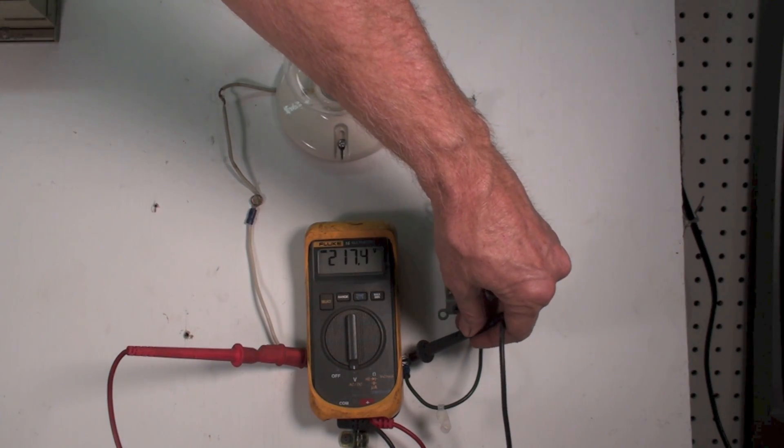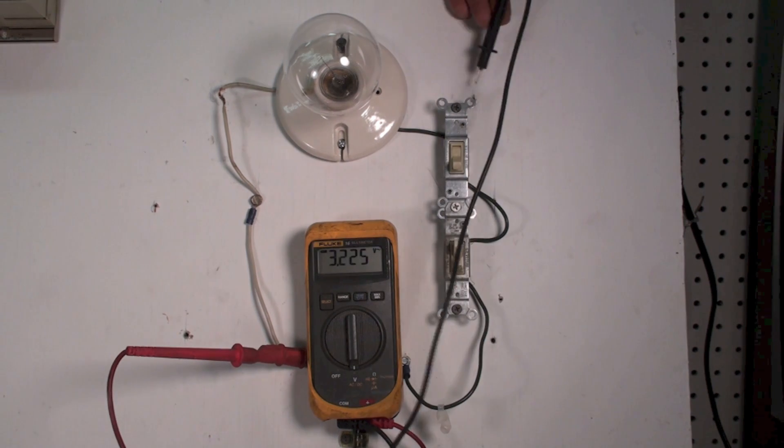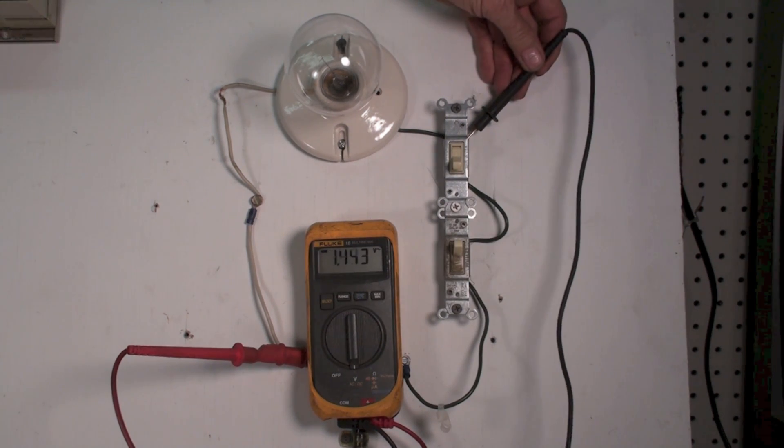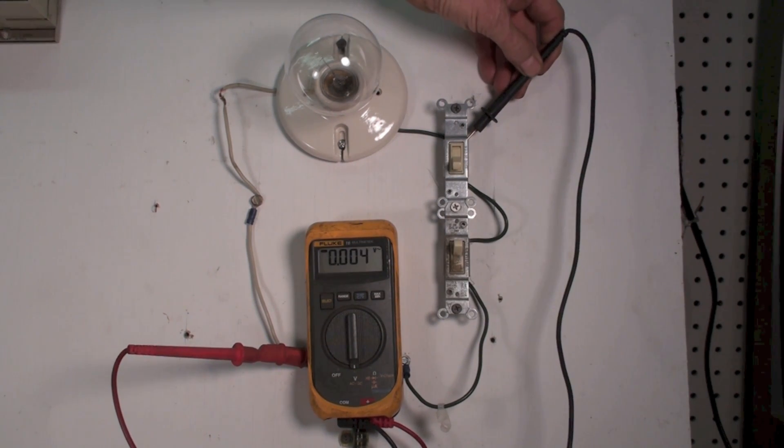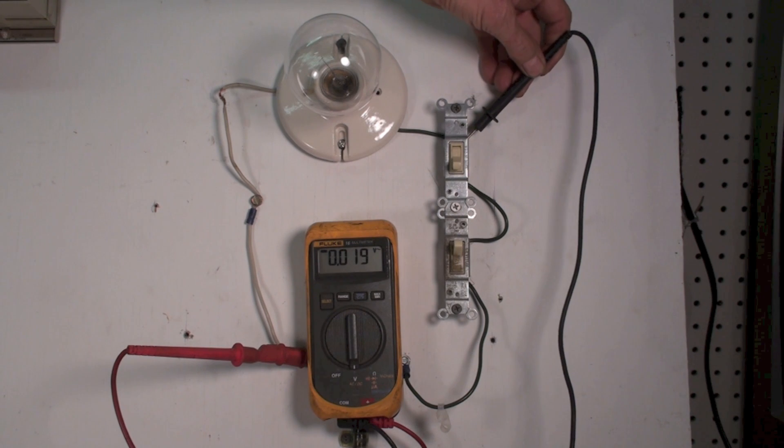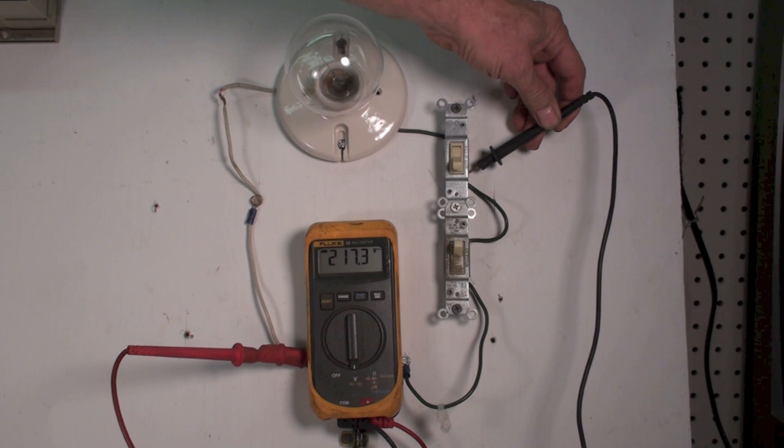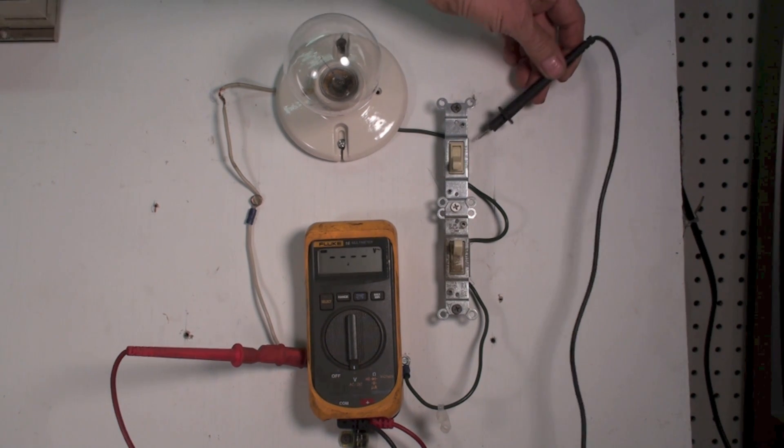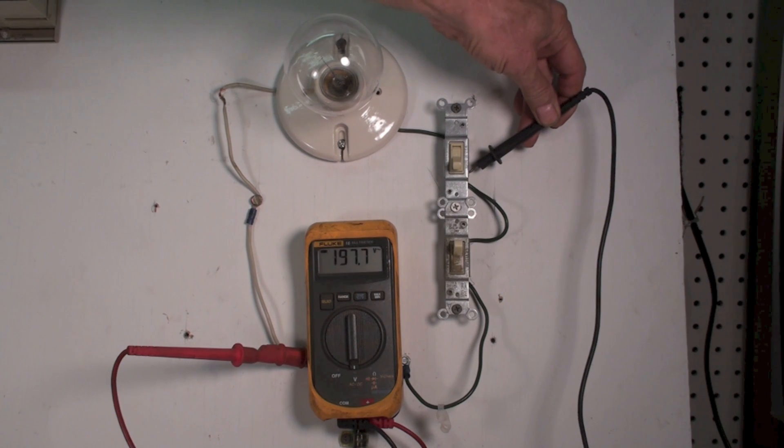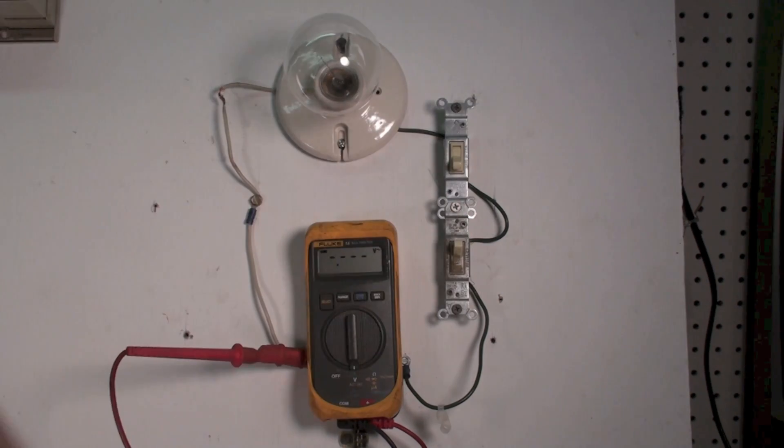I have power. I go across the load, I don't show any power. I go here and I show 240 volt power. So I know the switch I just bypassed is a switch that is off. That's how that actually works.